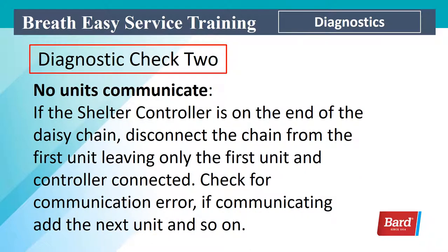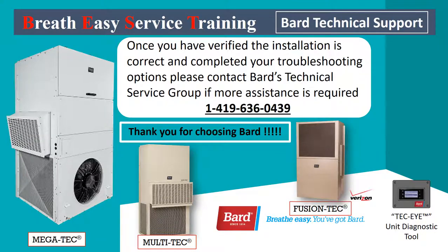If you have no units communicating, if the shelter controller is on one end, take the unit next to the shelter controller. If it's not on an end, disconnect everything beyond the controller so your controller is only connected to one unit. Check for a communication error — if it's communicating, add the next unit and so on until you locate the communication problem. Thanks for watching this Breathe Easy service training edition. Once you've verified the installation is correct and completed your troubleshooting options, please contact Bard Technical Service Group if more assistance is required: 1-419-636-0439. Thank you for choosing Bard.